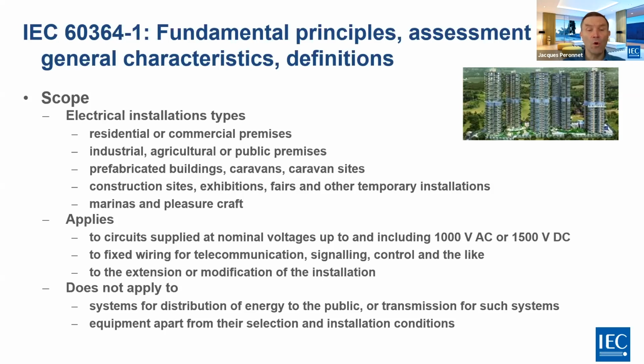It applies to all circuits supplied at a nominal voltage up to and including 1000 volt AC or 1500 volt DC. So this is what we call the low voltage limits. It applies to fixed wiring for telecommunication, signaling, control, and the like, and to the extension or modification of the installation. It doesn't apply to systems for distribution of energy to the public or transmission for such a system, which is covered by some other technical committee, and equipment, apart from their selection and installation conditions.